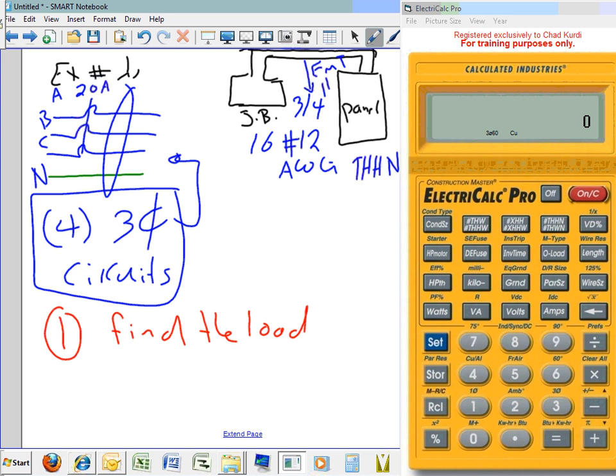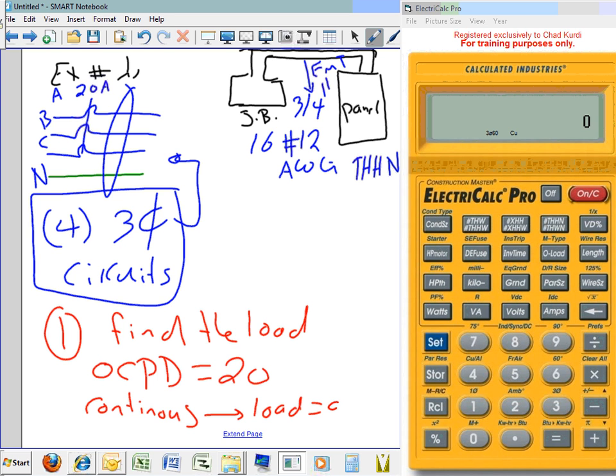80%, thank you. So we start by saying overcurrent protection device equal 20. Because it's continuous, I am limited to then load equal 0.8 times 20. What would that give you guys, 0.8 times 20? 16 amps. So from the get-go, I'm limited to 16 amps because it's continuous load. Light, continuous load, right? I'm limited to 16 amps on these. So what does that mean actually? When you start circuiting your lights, here's 1 amp, assuming each one of these lights is an amp. So you can only put 16 lights on that circuit breaker.